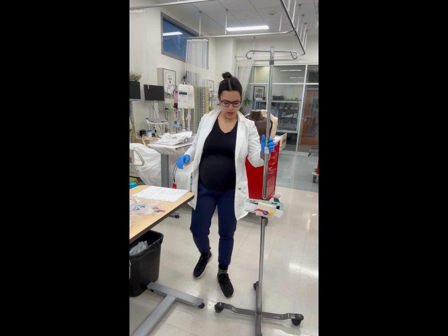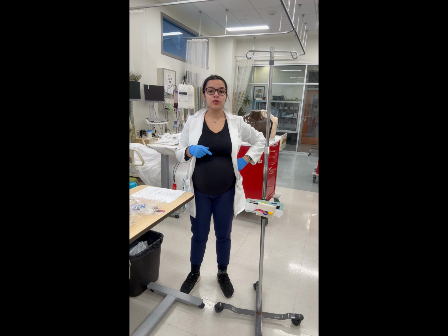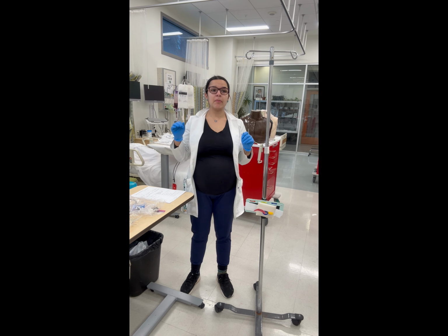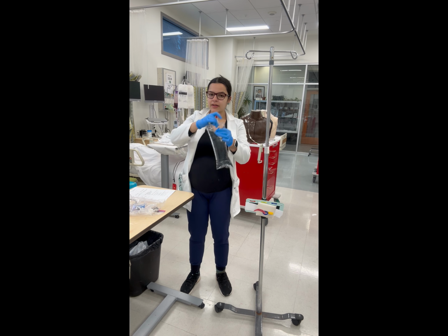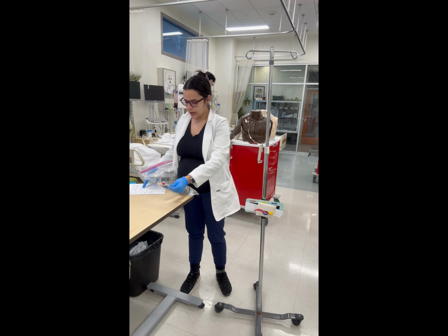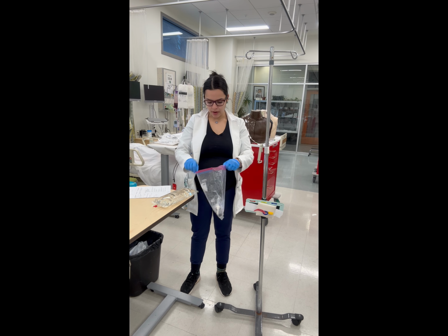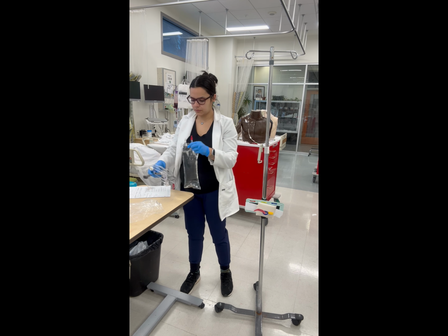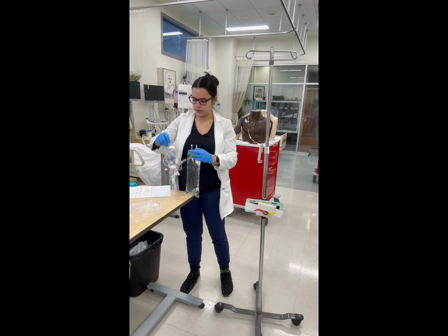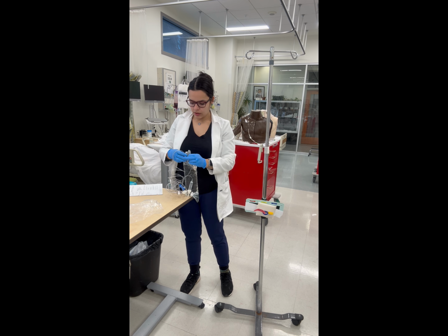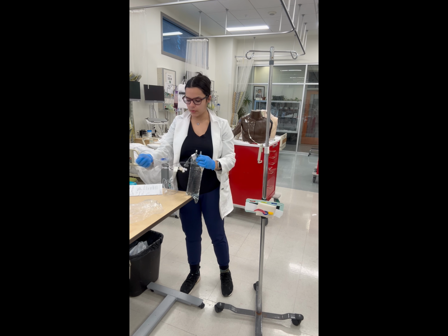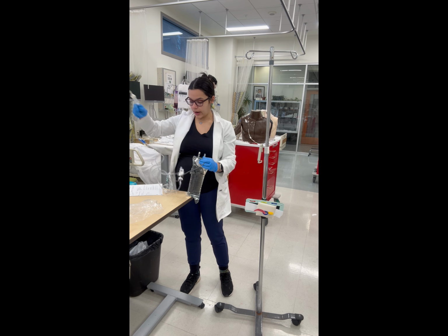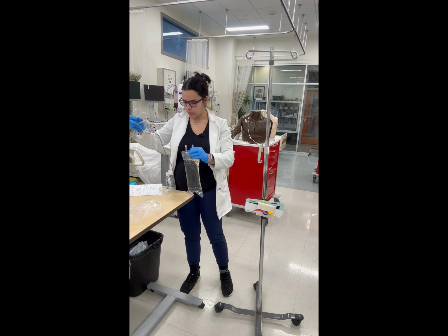All right, so now that I have that ready to go, I need to get my tubing primed. Remember, I don't wanna put the IV bag inside of the pressure bag and then inflate the pressure bag and prime my tubing. I want to prime my tubing with gravity beforehand, okay? So remember, the bags in the lab have been spiked before, so be careful with those red caps. They like to pop off. I'm going to take my red cap off. And your tubing set has probably been used a few times before, so you're more likely to get some more air, but we're gonna go with what we've got here, okay?